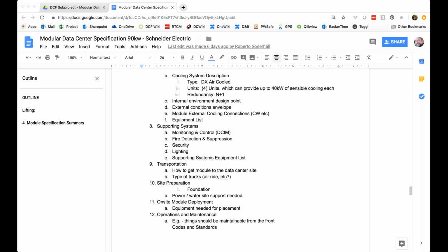At the moment, the new refrigerants are all flammable, which in the data center might not be that much appreciated. So it might be that in the next close future, there is a shift from direct expansion to chill water, at least for Europe, not for the US, where there is not such stringent regulation as in Europe for the refrigerants. So for sure the DX is okay, but in my opinion, we shall keep the door open also for chill water.